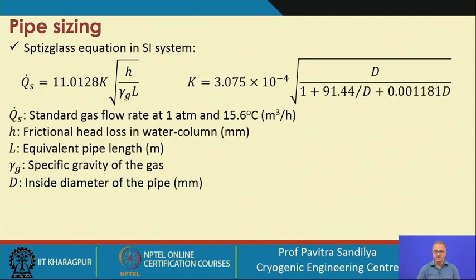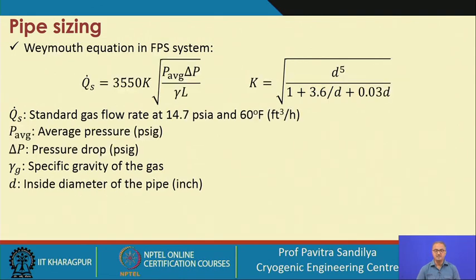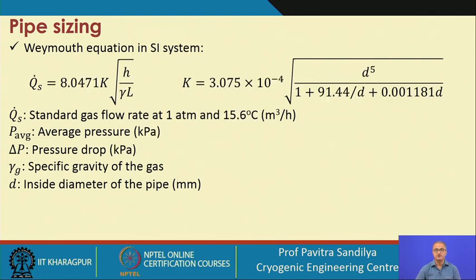In SI units, the same Spitzglass expression and the Weymouth equation can be used to find capacity. The Weymouth equation is used for higher flow rates and the Spitzglass equation for lower flow rates — these are the FPS and SI system versions respectively.